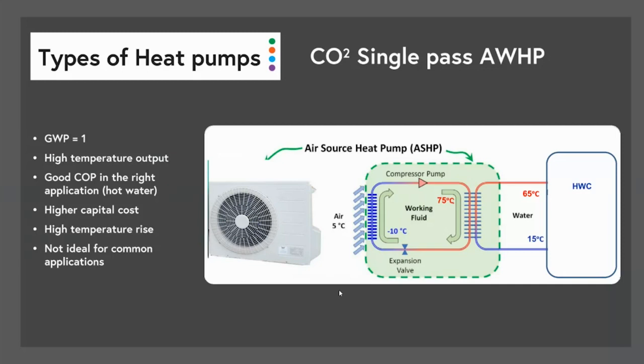But there are problems with CO2 heat pumps, and one of them is that they are quite expensive for what they are. And the reason they're expensive is because of the compressors. They run at extremely high pressure, so they're very heavy duty construction, quite expensive, and very expensive to replace. To give you an example, a CO2 heat pump runs at somewhere between 100 and 110 bar of pressure, which is about 10 to 11,000 kPa, or about 1,600 psi. So very, very high pressure.